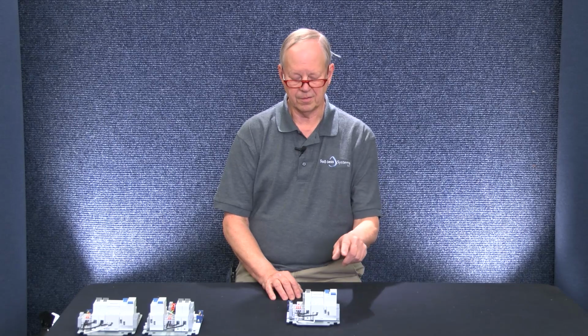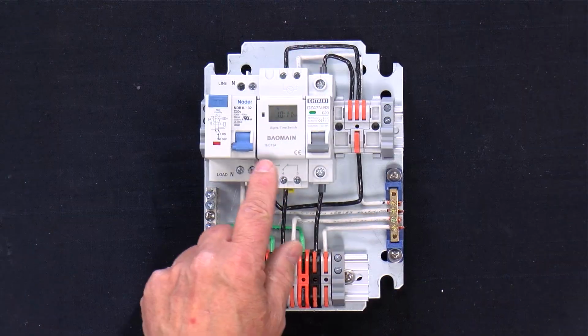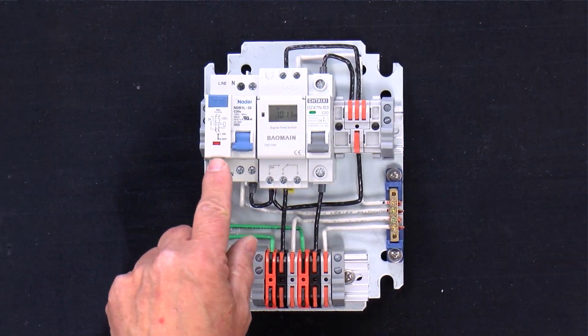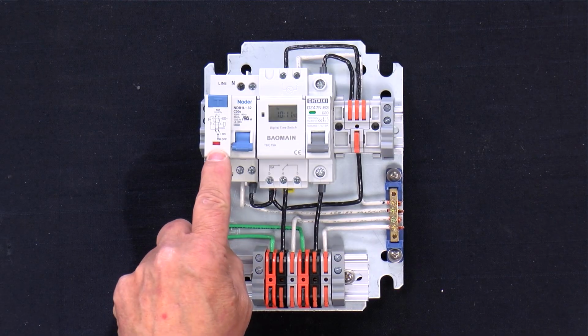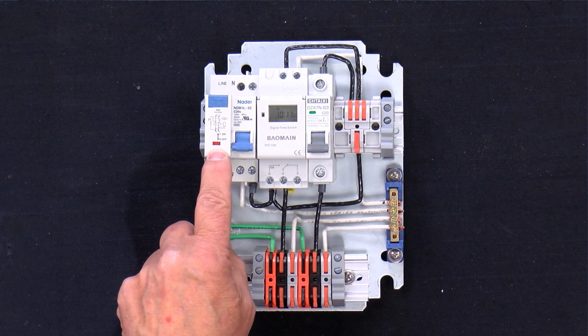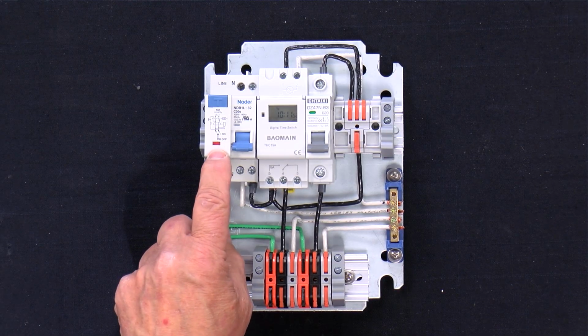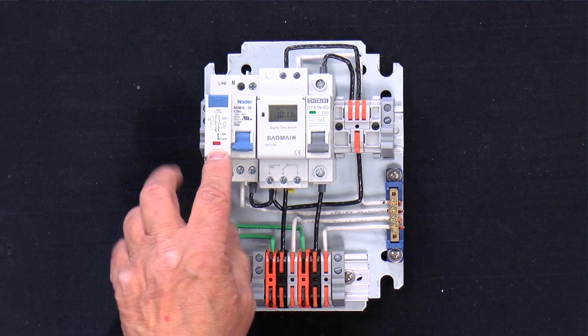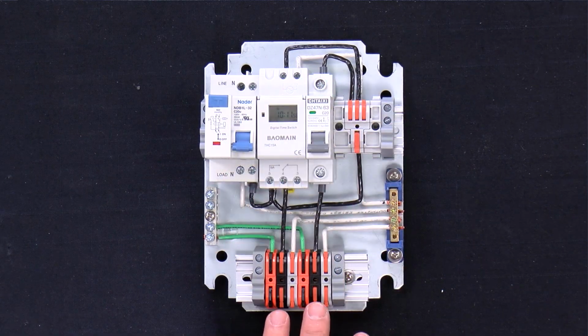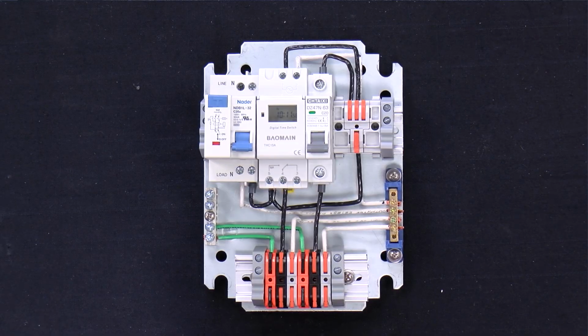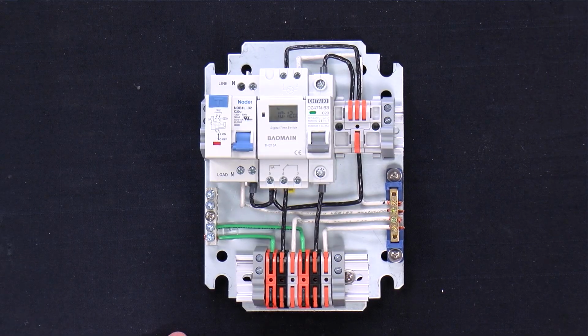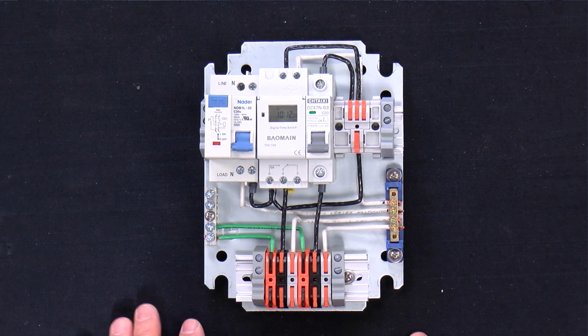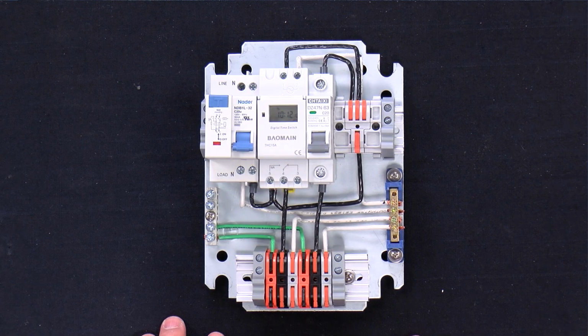In the close-up frame, here are the major components. All local control panels have a GFCI breaker. The GFCI breaker protects all of the other circuits attached to it to keep the operator from any kind of electrical shock. If there is a ground somewhere, the GFCI breaker will trip and shut things down, rendering the unit safe.